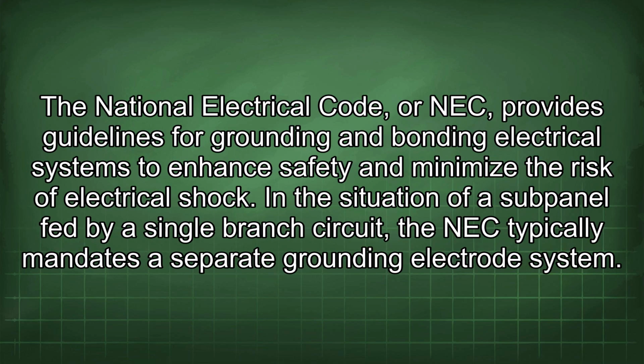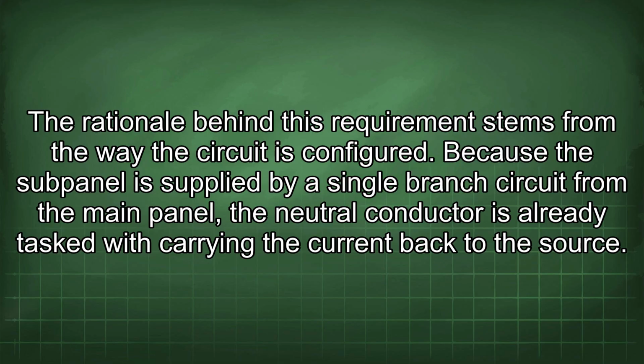The National Electrical Code, or NEC, provides guidelines for grounding and bonding electrical systems to enhance safety and minimize the risk of electrical shock. In the situation of a subpanel fed by a single branch circuit, the NEC typically mandates a separate grounding electrode system. The rationale behind this requirement stems from the way the circuit is configured. Because the subpanel is supplied by a single branch circuit from the main panel, the neutral conductor is already tasked with carrying the current back to the source.